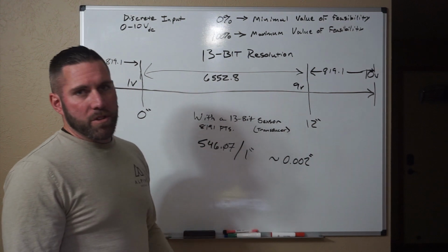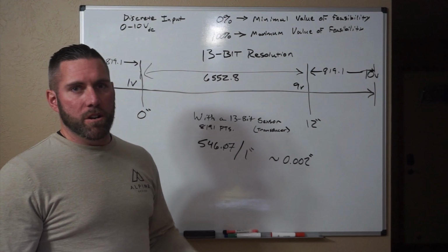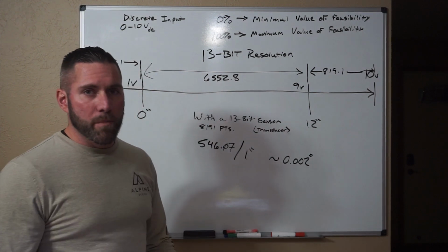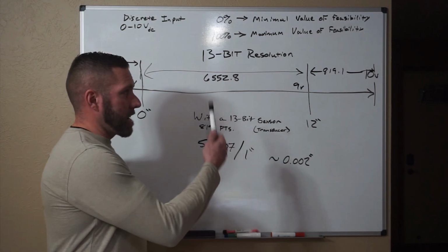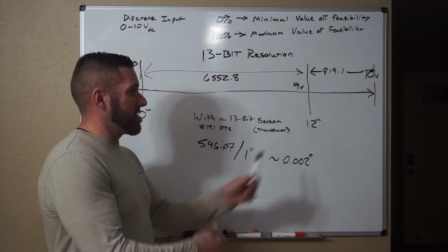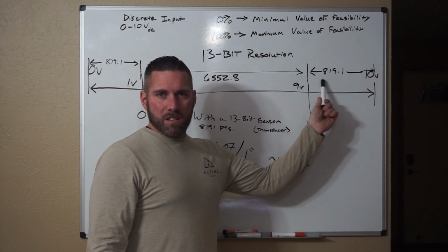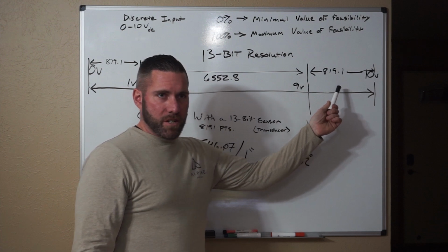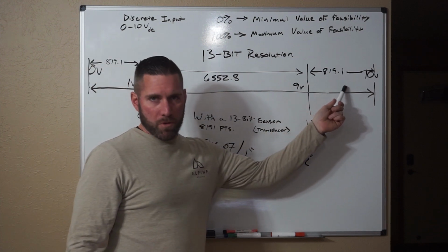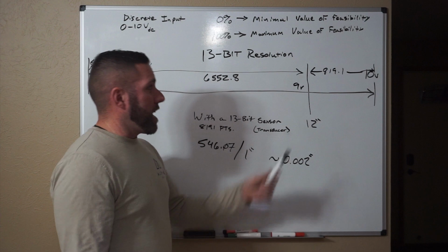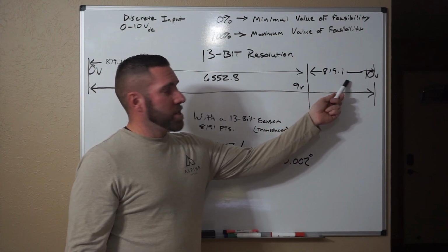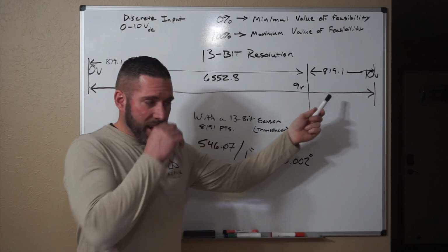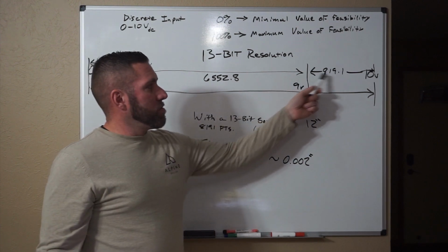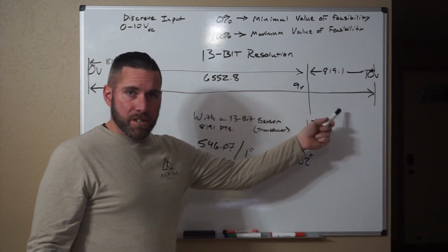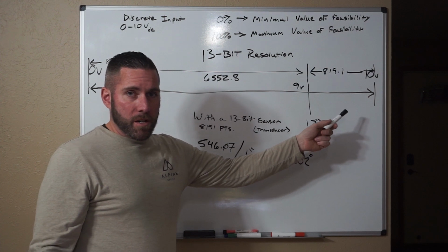You have to know how to read the drawings. You have to know what the P&ID charts say. You have to know what kind of equipment you actually have to figure out what's going on with this. You're not going to see this. This is all in the automation control side of the house. This is not going to be on any tools. I have a tool that I have used recently to actually get these values though, and these values are only good if you set your significant digits on the PLC that's reading them. And I will show you what that tool is.